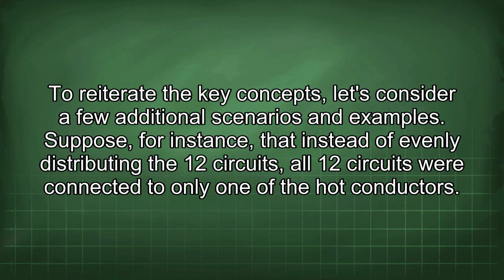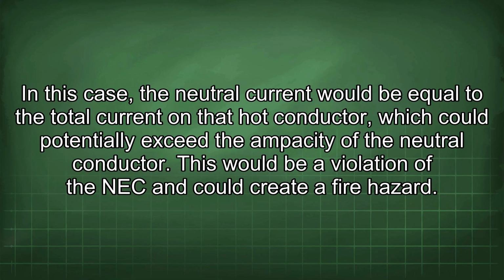To reiterate the key concepts, let's consider a few additional scenarios and examples. Suppose, for instance, that instead of evenly distributing the 12 circuits, all 12 circuits were connected to only one of the hot conductors. In this case, the neutral current would be equal to the total current on that hot conductor, which could potentially exceed the ampacity of the neutral conductor. This would be a violation of the NEC and could create a fire hazard.